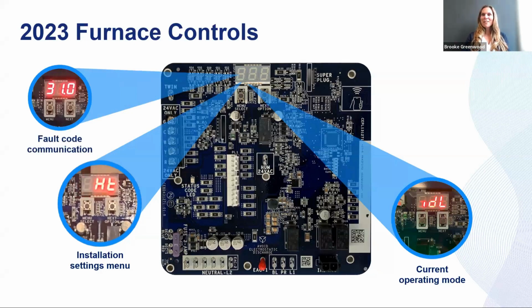We talked about the fault code communication. No longer do you need to count flashing lights, you have access to the last 7 faults on the equipment through the control board. You'll also notice a 3-digit fault code. We all know pressure switches are fault code 31, but now you'll see 31.1, 31.2, which gives more detail on where the fault occurred, like whether the pressure switch opened or is stuck closed. This gives you more information when you walk up to the equipment so you can troubleshoot faster, get the homeowner up and running, and move on to the next job.